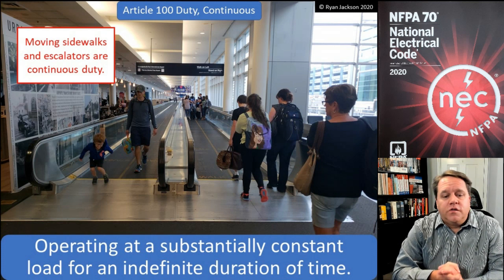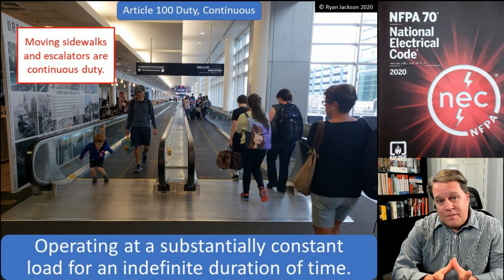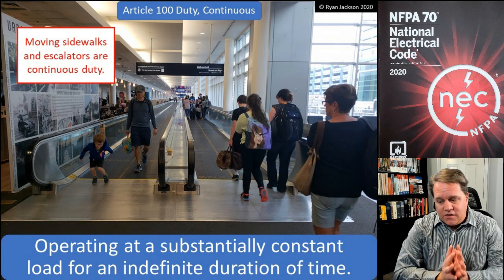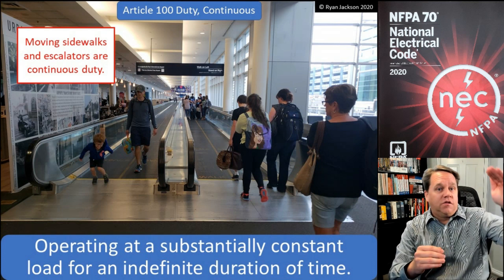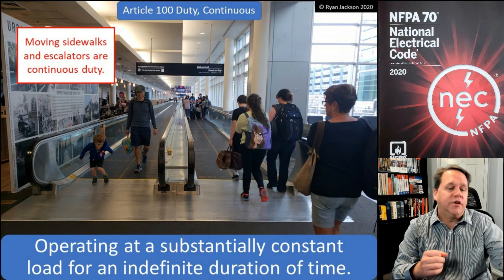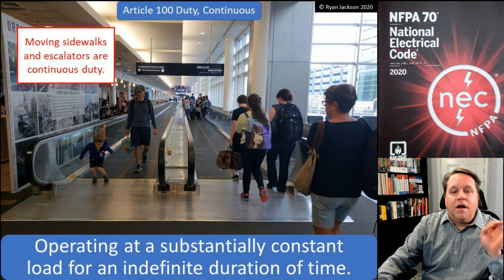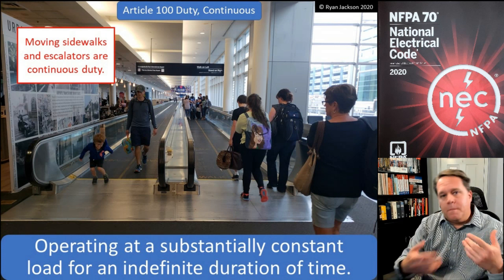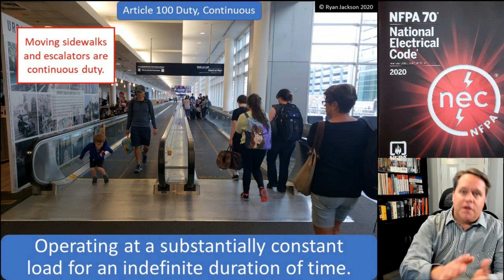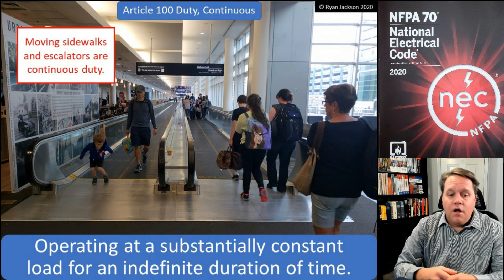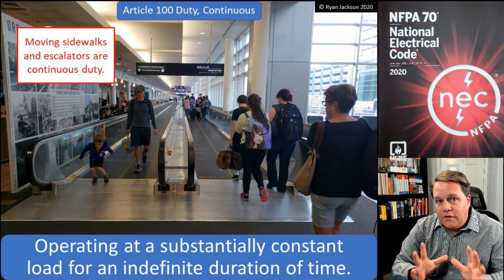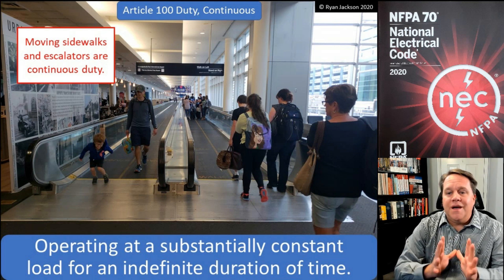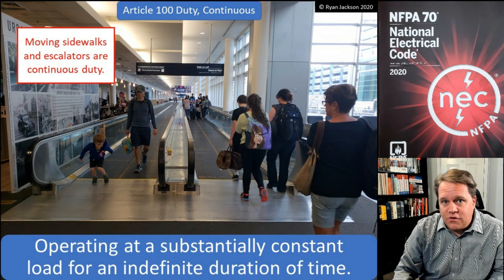Starting with the simplest — continuous duty: something that operates at a substantially constant load for an indefinite duration of time. The best example I can think of would be the moving sidewalk at the airport or an escalator. They don't have a definite starting or stopping point; they're continuously going forever at a substantially constant load. People get on and off, sure, but it's pretty well expected. Most motors per 430.22(e) are considered continuous duty motors unless they have a definite stopping and starting point.